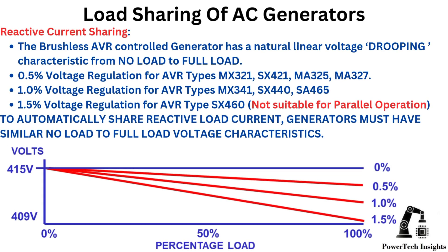Reactive current sharing. The brushless AVR control generator has a natural linear voltage drooping characteristic from no-load to full-load: 0.5% voltage regulation for AVR types MX321, SX421, MA325, MA327; 1% voltage regulation for AVR types MX341, SX440, SA465; 1.5% voltage regulation for AVR type SX460, not suitable for parallel operation.